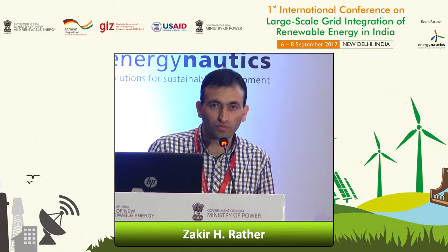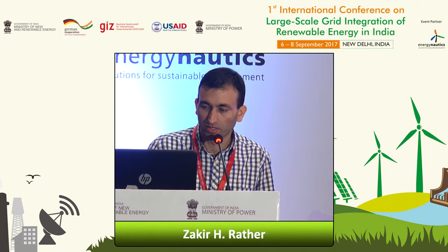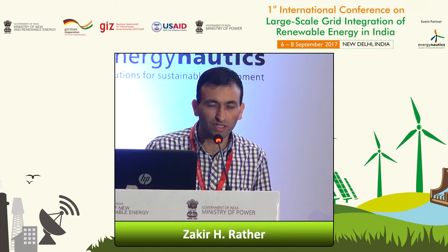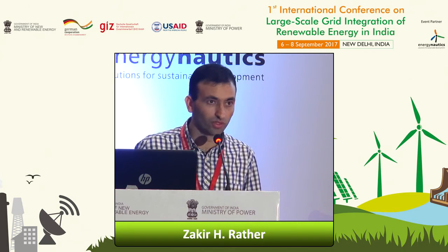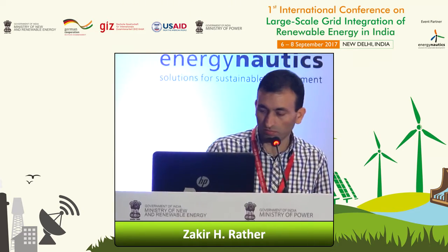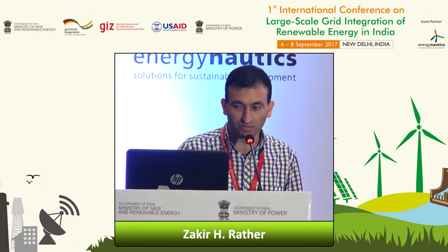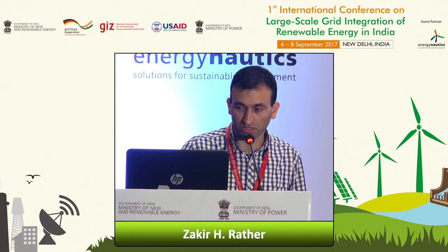We have 4 types of wind turbines. It started with type 1, type 2 wind turbines, which were induction generator based wind turbines, which were followed by variable speed wind turbines, type 3 and type 4, which are currently in the market. But still, at least in some countries, there is significant penetration of type 1, type 2 in the system.